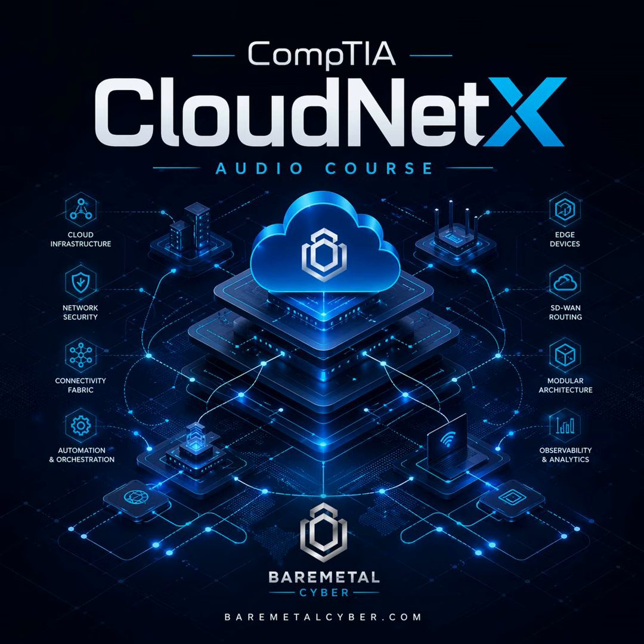To close episode 65, titled MDF/IDF Design, Maintainability, Cable Strategy, and Operational Reality, the core lesson is that closets and cabling strategy are uptime controls because they determine how quickly you can recover, how safely you can change, and how often physical issues create intermittent faults. The MDF is the central distribution and demarc aggregation point, while IDFs are local closets serving floors or zones, and both must be designed for growth with planned pathways, consistent labeling, and maintainable layouts.